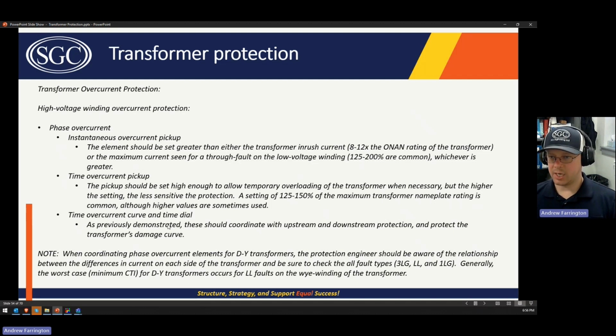And then the time dial, so that's just to set the pickup level, but then we also need to set the time dial and the curve appropriate such that it protects that transformer damage curve that we talked about during the Aspen one-liner course. And it needs to coordinate with any upstream or downstream protection.